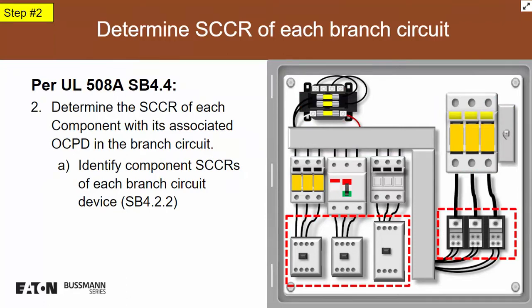Step number two, determine the SCCR rating of each component with its associated overcurrent protective device. As you can see to the right, the power distribution block has a rating by itself. But if we have a fuse or a circuit breaker ahead of it, that's its associated overcurrent protective device. So what is the true rating of that power distribution block? Is it 10,000 amps, or 65,000 amps, or 100,000 amps? That's what we have to do. Make sure that we take that component and tie it to the associated overcurrent protective device to get that combination rating that we're looking at.